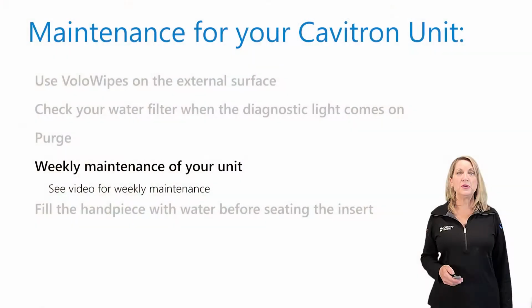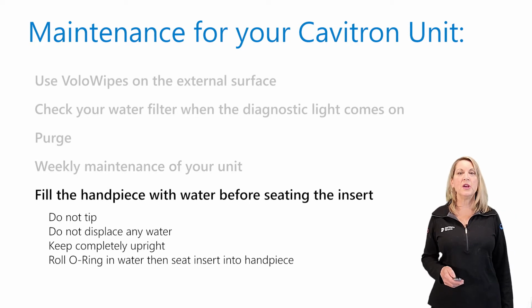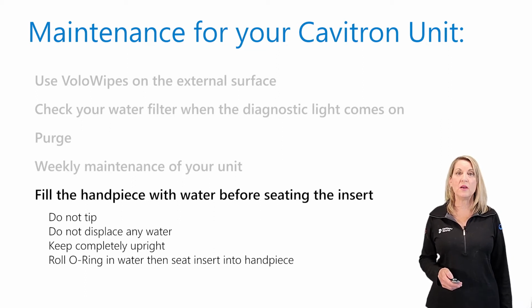The proper way to use your Steri-mate handpiece is to fill up the handle with water before inserting your Cavitron insert. Do not tip the Steri-mate on an angle, as this will allow air bubbles to enter and create hot spots that can cause damage to both the Steri-mate and the insert. Keep the Steri-mate completely upright to avoid this. It is recommended that you roll the O-ring across the bubble of water at the top of the Steri-mate, as shown in the next video, to lubricate it before placing it into the handle.